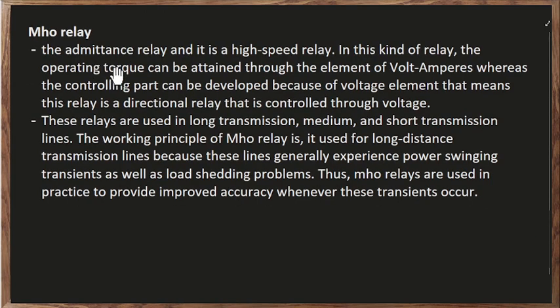Then the Mho relay or the admittance relay, and it is a high speed relay. In this kind of relay, the operating torque can be attained through the element of volt amperes, whereas the controlling part can be developed because of the voltage element. That means this relay is a directional relay that is controlled through voltage. So the Mho relay can be controlled through voltage, but it is also a directional relay.